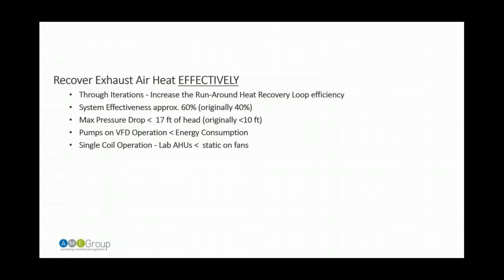And we'll show in the next couple slides, but we've got a single coil operation for the lab air handlers. And I know this might not be the best strategy for colder climates. In the lower mainland, we're not as worried about freezing, so we might not have a preheat coil that you might look at for colder climates where you're at -40 or some other temperature like that in Winnipeg or any of the northern climates. And so we were a lot more comfortable knowing that we'd be okay using water in our system and just using the one coil to heat and cool. And so I'll show how we did that as well.